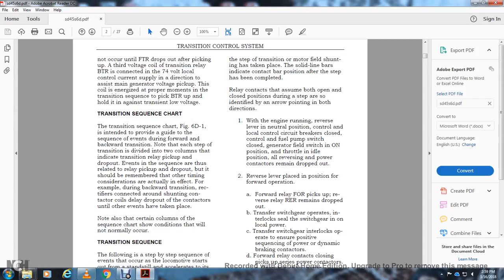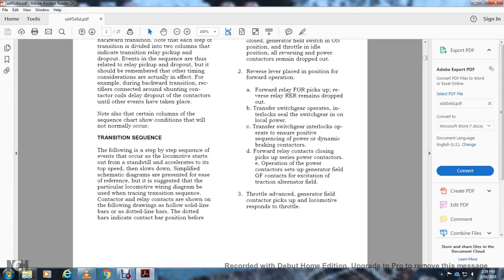Alright, the transition sequence chart, figure 6D1, is intended to provide a guide to the sequence during forward and backward transition. Note that each step of the transition is divided into two columns that indicate the transition relay pickup and dropout, with the events of the sequence that are related to the relay pickup and dropout. But it should be remembered that other timing considerations are actually in effect. For example, during backward transition, rectifiers connected around the shunting contactor coils delay the dropout of the contactors until the events have taken place. Note also that in certain columns of the sequence chart, the conditions shown will not normally occur.